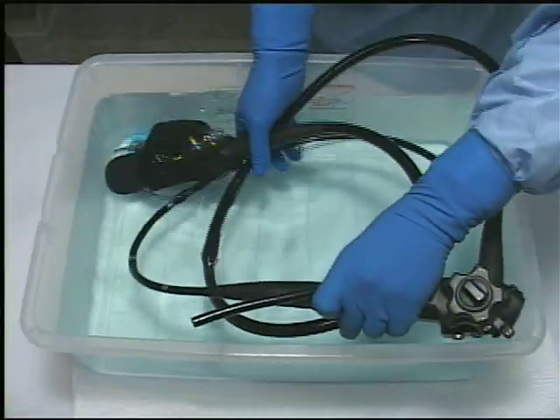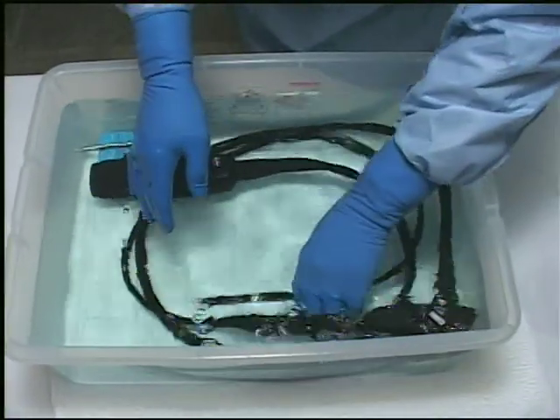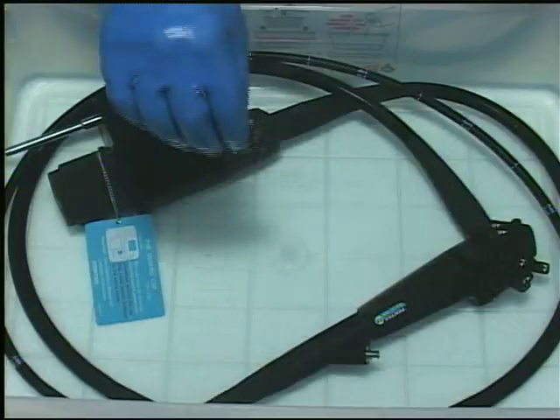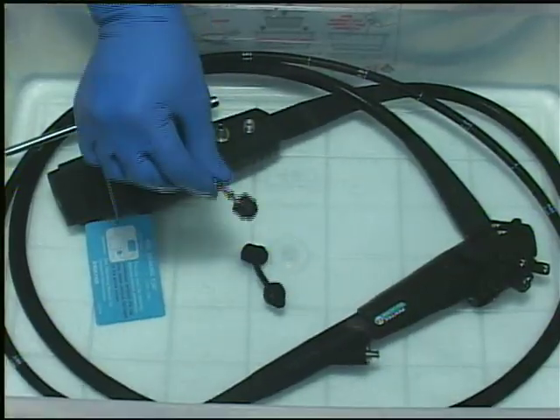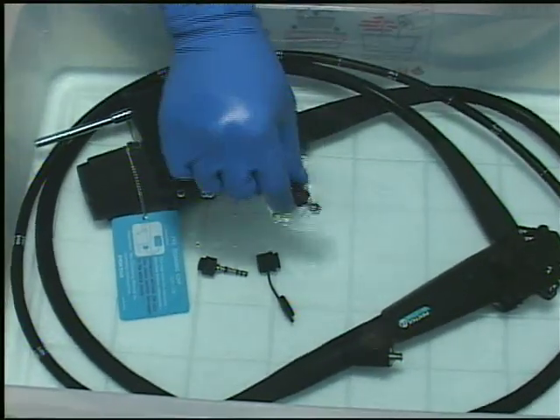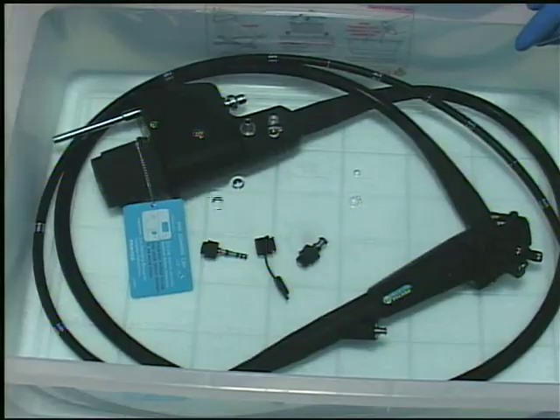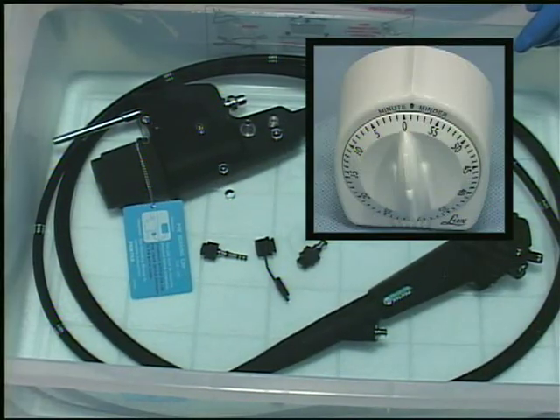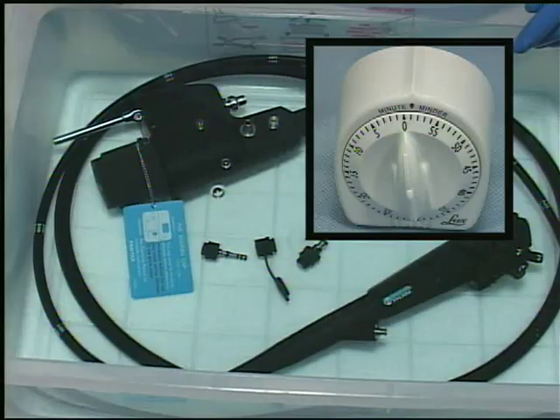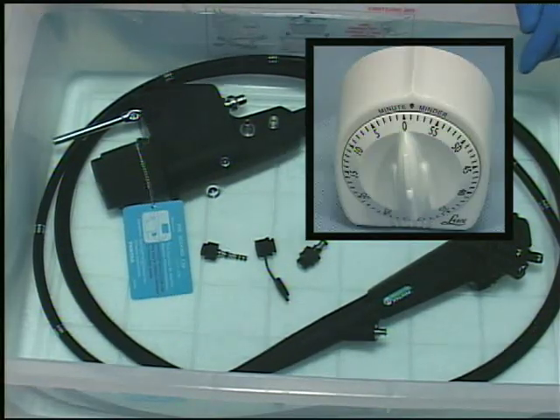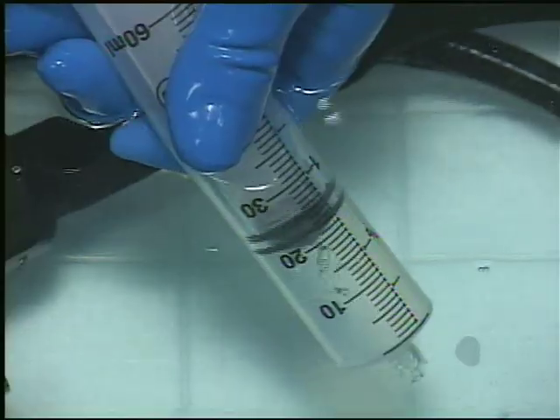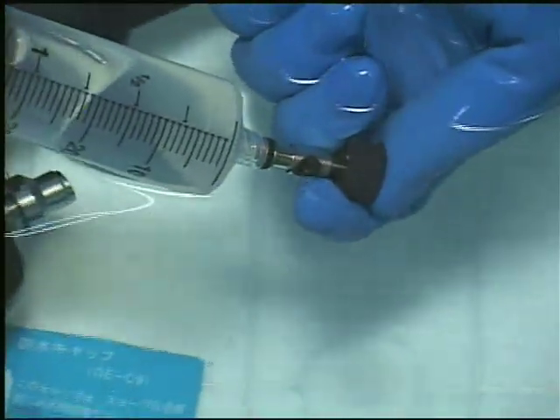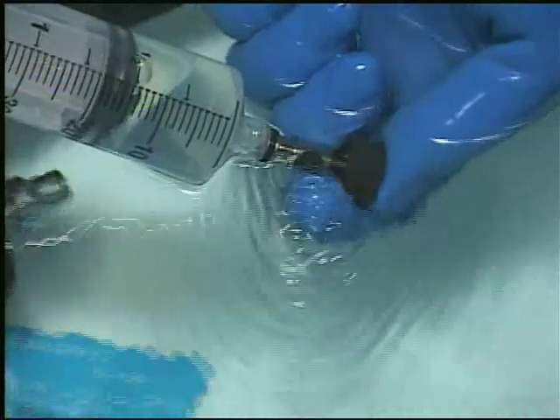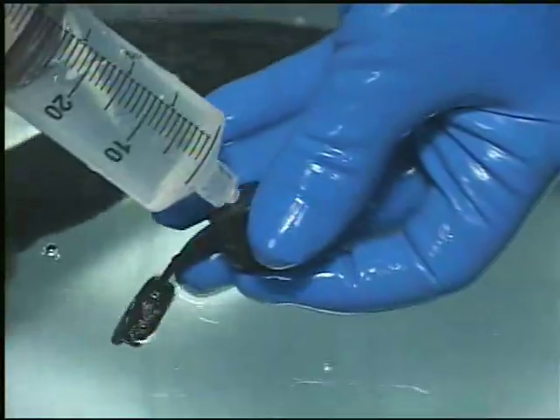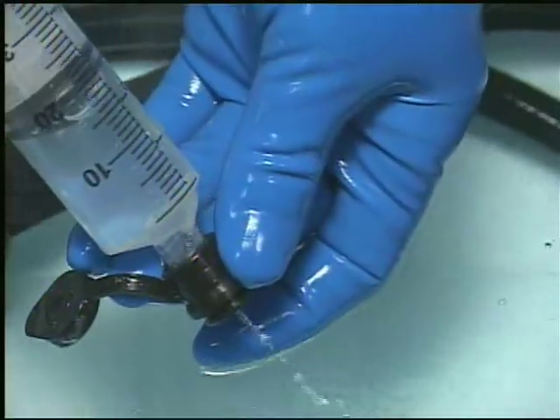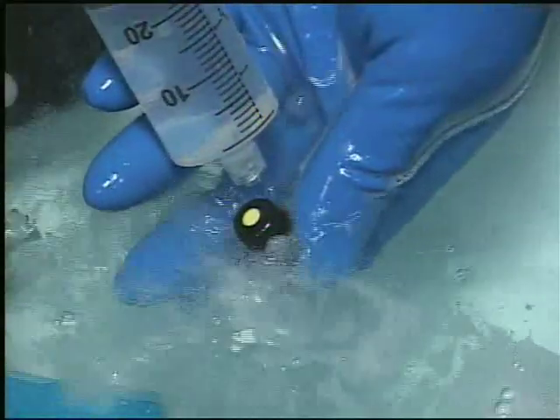Immerse the endoscope in detergent solution. All scope components, including the suction valve, air-water valve, inlet seals, etc., which were previously removed, can now be transferred to a cleaning solution in the decontamination area. Allow all items to soak in the enzymatic detergent solution for the time period recommended by the manufacturer of the enzymatic detergent. While fully immersed, manipulate valve mechanisms and inject detergent with a syringe into or through removable scope components. This will remove air bubbles and provide for better exposure of all surfaces to the detergent.